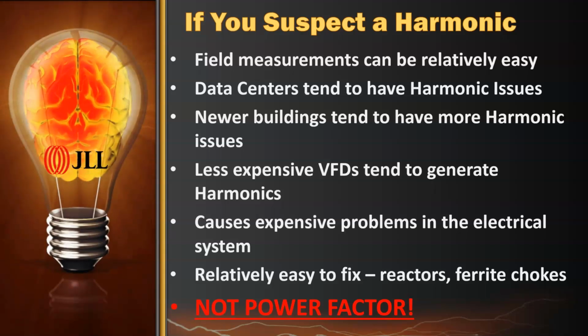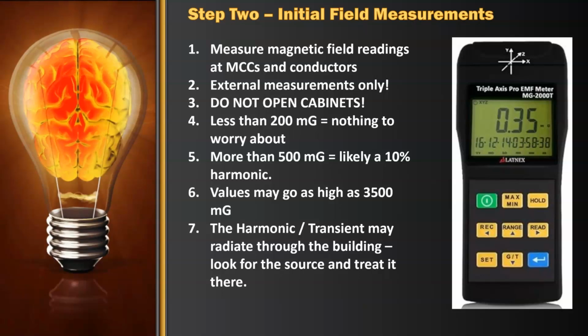So if you suspect a harmonic, this is the meter that we use. This is an EM meter, an electromagnetic meter. It's the same sort of thing you would use for measuring EM radiation on anything, really. You remember from the earlier graphic where I showed that the harmonic energy got pushed out to the outside of the conductor? Well, when that happens, it makes the magnetic field around the conductor a lot stronger. And so this gives us a fairly quick and easy way to see whether or not you have a harmonic present in your building or in your system.